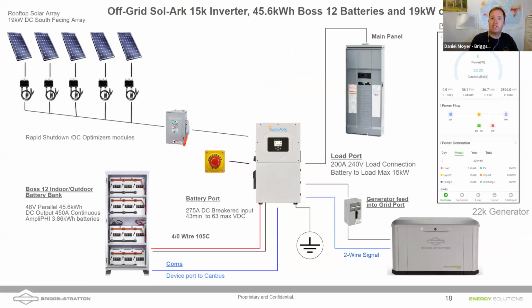Why? Because if we're going to size your solar system, this map behind me is actually the solar insolation that the Earth receives during the worst month of the year, right? During January or December, at least in the Northern Hemisphere. And so we size your solar on your off-grid property to find a balance between the two. If I size it for what this map says, your solar is going to be way oversized for summer. So what we want to do is leverage the generators in the dead of winter when we've had a big storm. We can start that generator up using the 2-wire signal, charge up the batteries, and then shut the generator off.